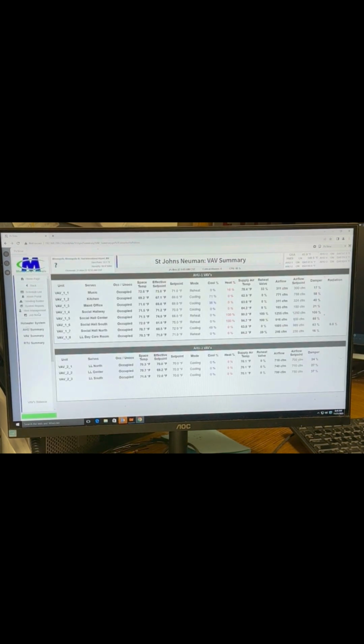Got it. And we haven't even looked, if I go to the second VAV, VAV 2-1 should be tied to AHU 2's schedule, but it may not be. It is tied to the AHU 1 VAV schedule. So there is a problem there. It's improperly scheduled, yes. 2-1 is on, so this should be tied to air handler 2.